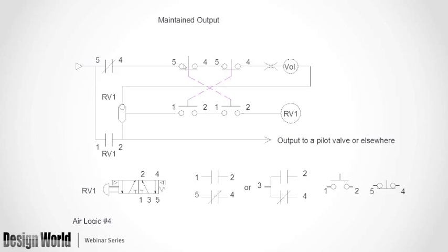So the air is going to come through here, charge the chamber, it comes down, and this is a shuttle valve. There's one ball in here. It's like two check valves with only one ball. If you're a hockey fan, you could relate that here we have a game of hockey and you only have one goalie. That ball can only cover one goal at a time. So when the air charges this chamber, it's going to push that ball down and seal off this side and bring the air from the top to the right, and then it's going to stop here. See, port one is plugged down below here.